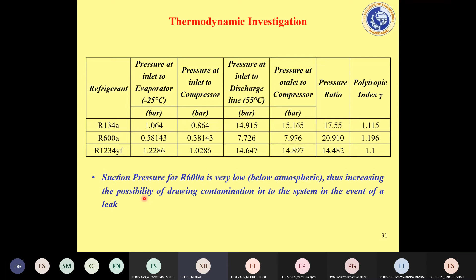Now, for the same refrigeration capacity, we have presented certain numbers over here. What is more important, you can calculate from the p-h diagram. I am not going to mention each and every number over here. What is important to us is the unit refrigerant effect. For R134A it is 140 kilojoule per kilogram, for isobutane it is 214, and for YF it is 103.35. Of course we are talking about the same capacity, so accordingly the mass flow rate would change.